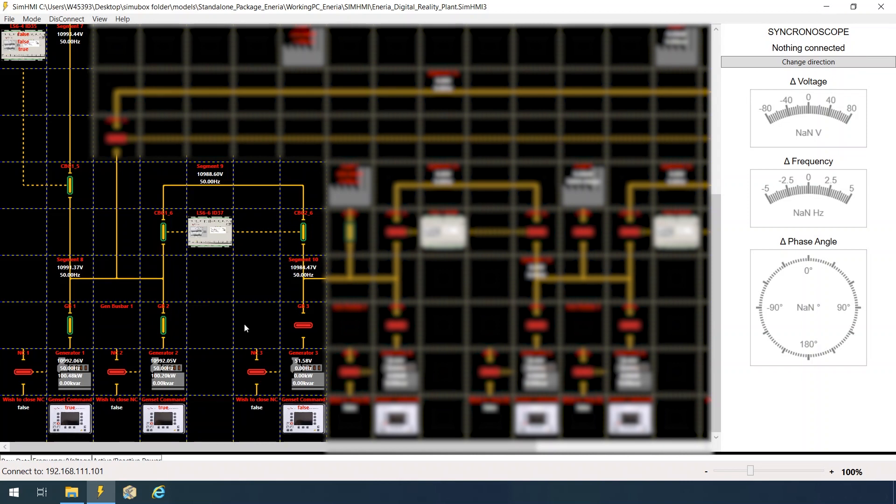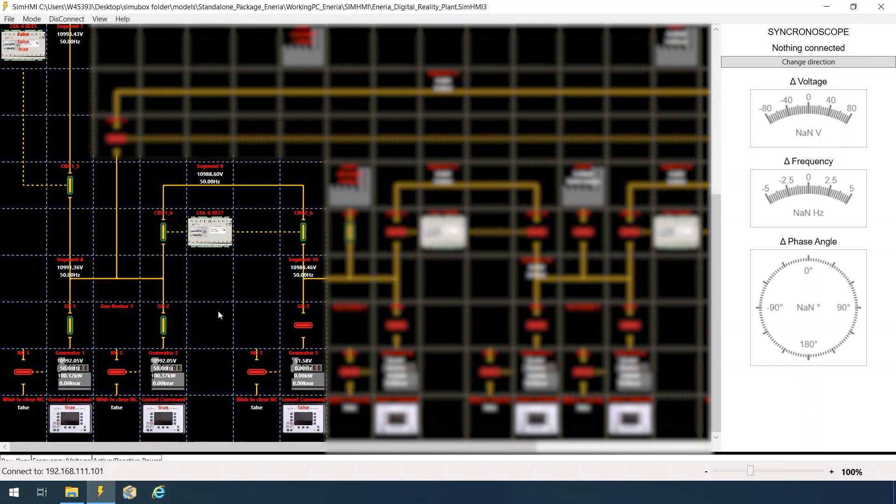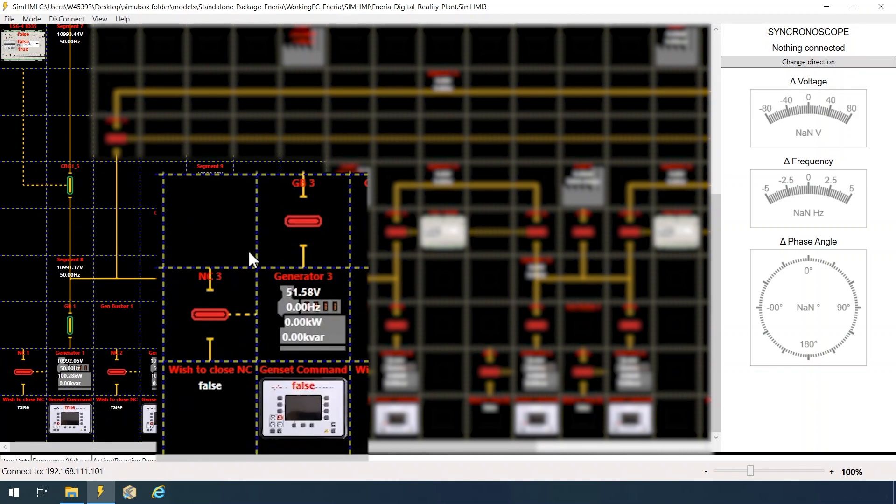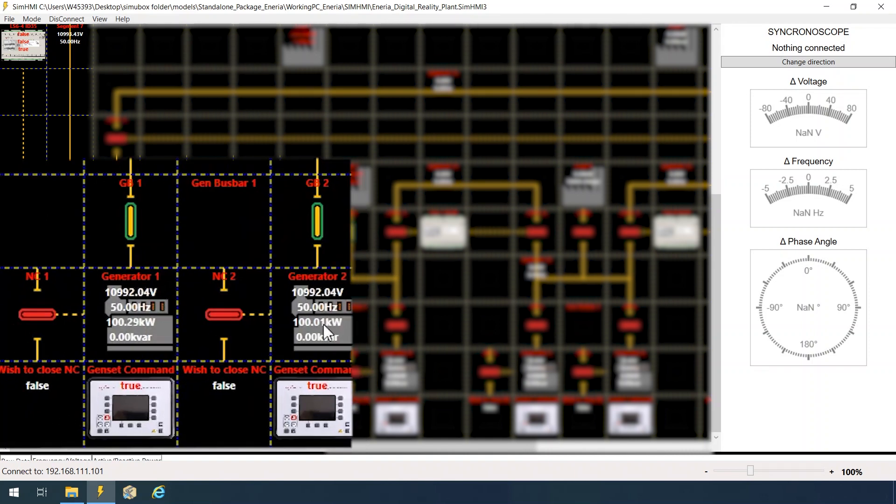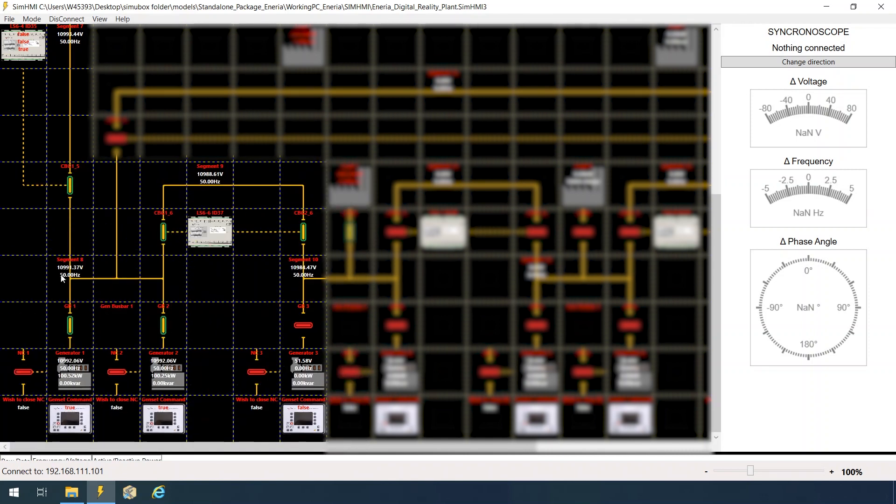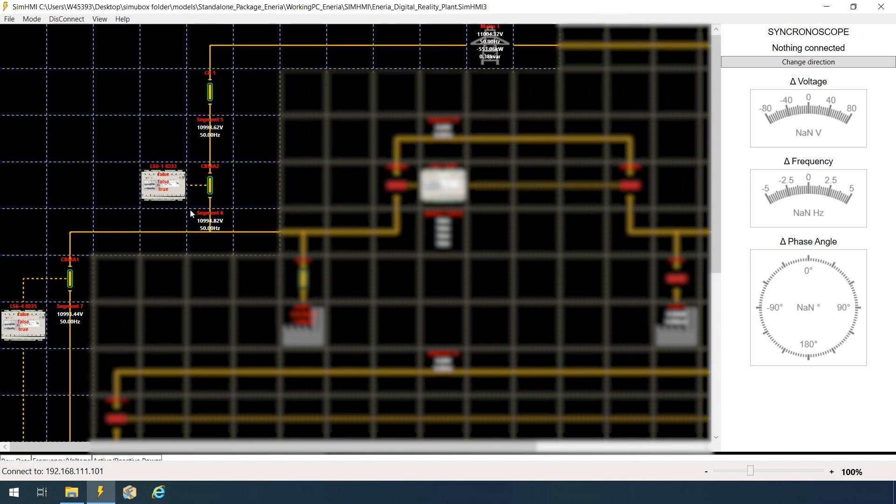Right now, the first two are running parallel to the grid. And the third one is stopped. We do not have neutral contactors closed because we are parallel to the grid.